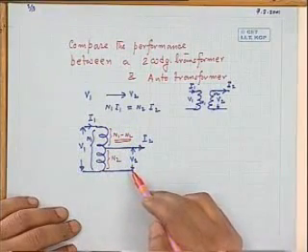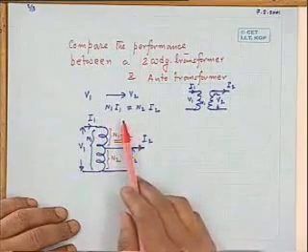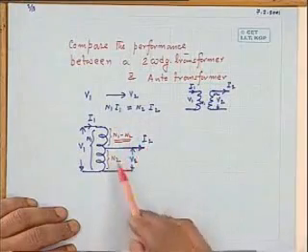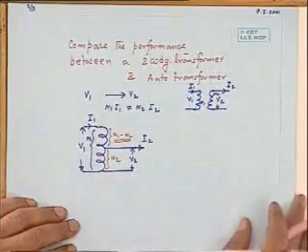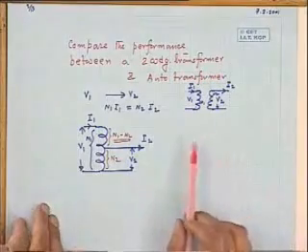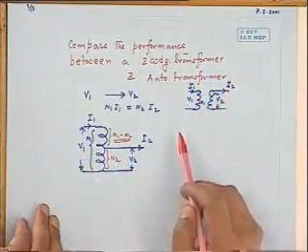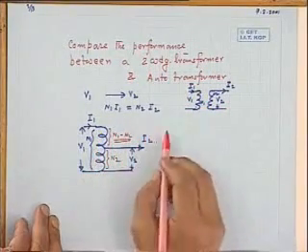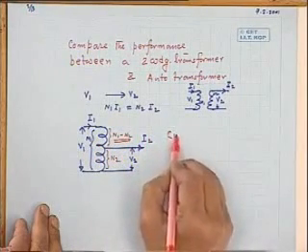use of an auto transformer may be advantageous, but with the turns ratio differing, I mean quite low or high, this may not be that much attractive. Now, that attractiveness or usefulness of an auto transformer can be understood by considering the amount of copper required in constructing an auto transformer and in constructing a two winding transformer for the same kVA and voltage ratios. So, how do I do it?